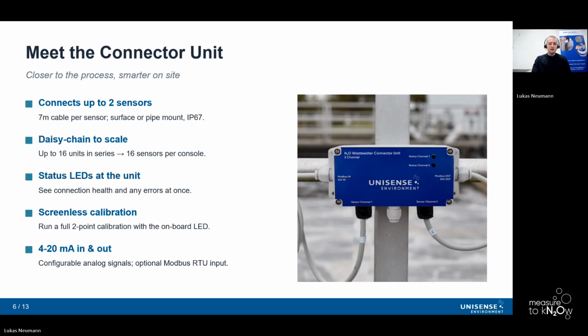I just enable the laser. Here we have status LEDs at the unit. Green is for power, blinking blue is for normal operation, and a solid red if something is wrong and needs your attention. So you can read the sensor health directly where the sensor is mounted without needing to go to the console. Then we have screenless calibration. The full 2-point calibration can be done using just LEDs, and more details on the next couple of slides in that regard.